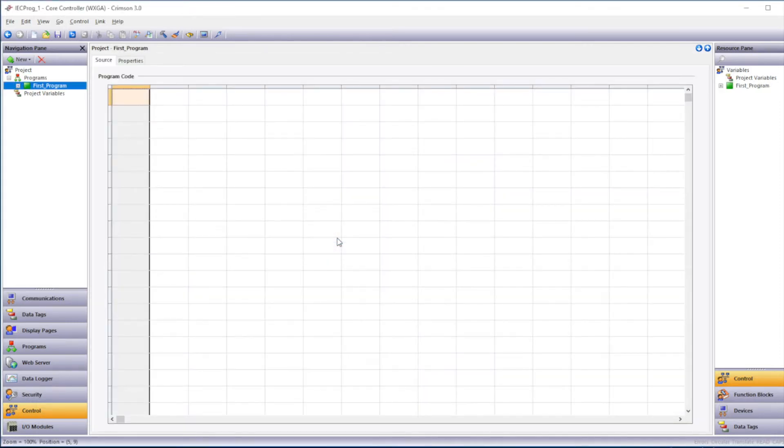Next, we'll click on the first program on the left-hand side in the Navigation pane. You'll notice that the default language is Function Block Diagram. We want to make our program with Ladder Diagram first, so I'll right-click on that Program 1 and delete it. To create a new program, I'll right-click on the Programs category there, and I'll click on New. Then select Main Program. The language will be Ladder Diagram. And then I'll type in the program name, which in this case I'll use First_Program. Then click OK.